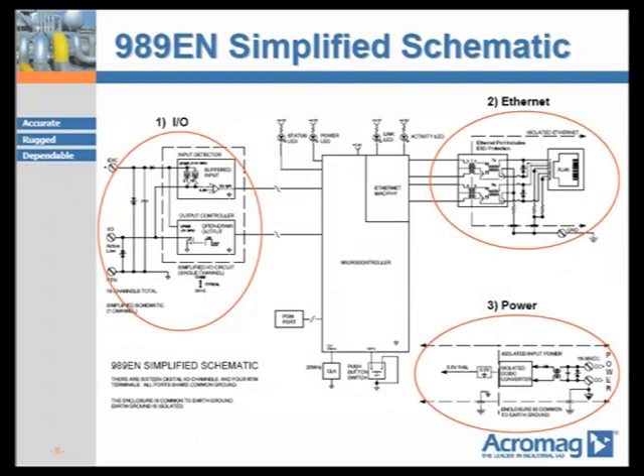This slide shows the simplified circuit diagram of the 989EN units, illustrating three things. First, all I/O channels have surge suppression technology built in. Second, the Ethernet 10/100 port includes built-in surge suppression and safety isolation from the rest of the circuit. Third, the power circuit also includes built-in surge suppression and safety isolation. This design offers three-way isolation between power, network, and I/O, and includes built-in electrical fast transient and electrical surge suppression technology on all channels and ports.